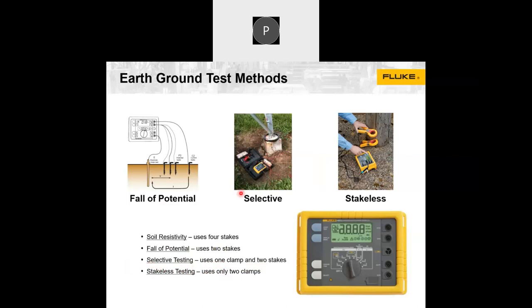This instrument comes with 2 clamps, 4 stakes, and 2 reels of cable to connect everything. So in places where you don't have facility to dig stakes, you can use these clamps - one sourcing clamp and one measuring clamp. It will inject the voltage and also measure the voltage, giving you the exact earth resistance of that system.